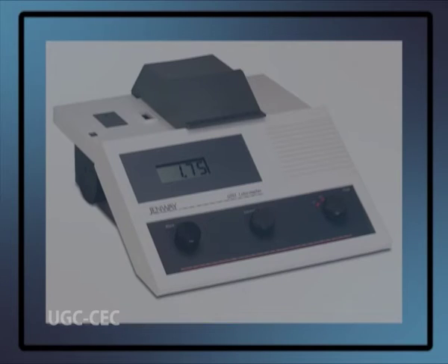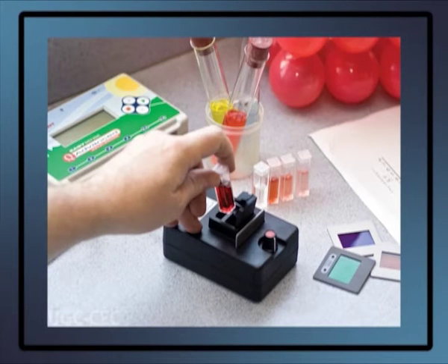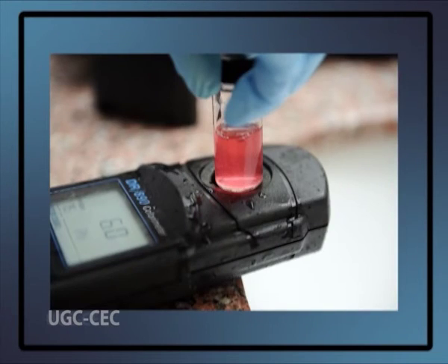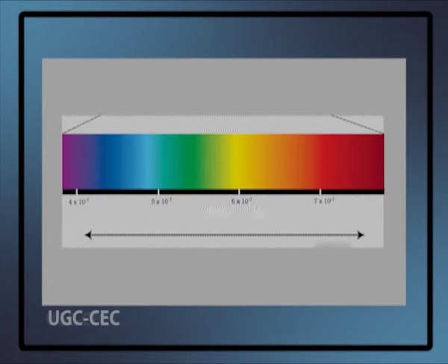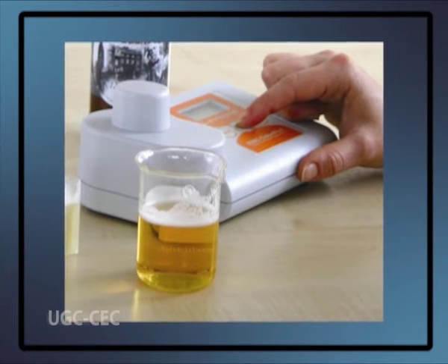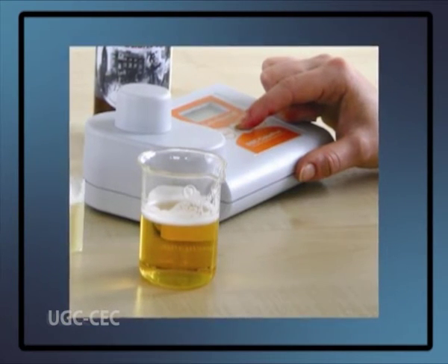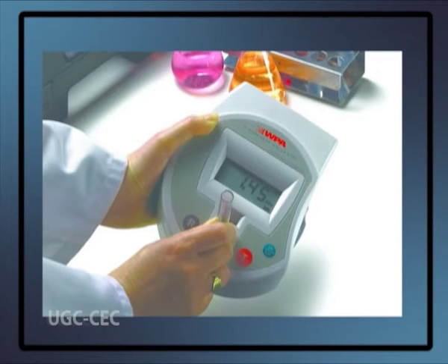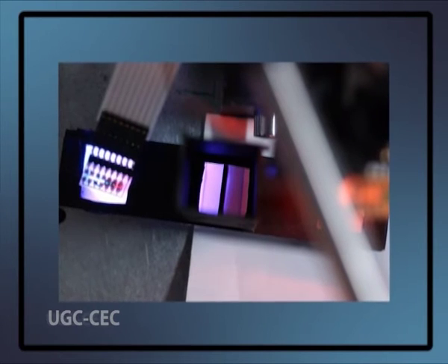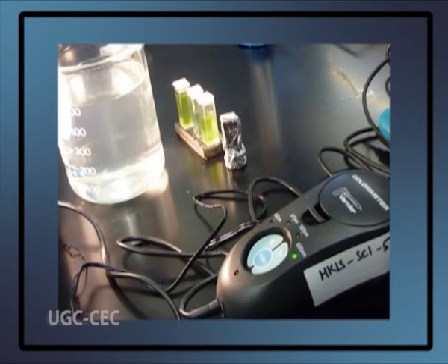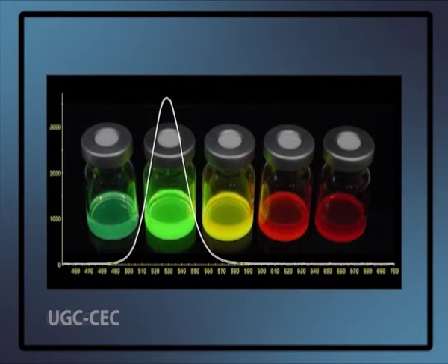Instrumentation. A colorimeter is any tool that characterizes color samples to provide an objective measure of color characteristics. A colorimeter allows the absorbance of a solution at a particular frequency of visible light to be determined. It relies on the principle that the absorbance of a substance is proportional to its concentration. A filter in the colorimeter is used to select the color of light which the solute absorbs the most in order to maximize the accuracy. Sensors measure the amount of light which has passed through the solution compared to the amount entering, and a display reads the amount absorbed.